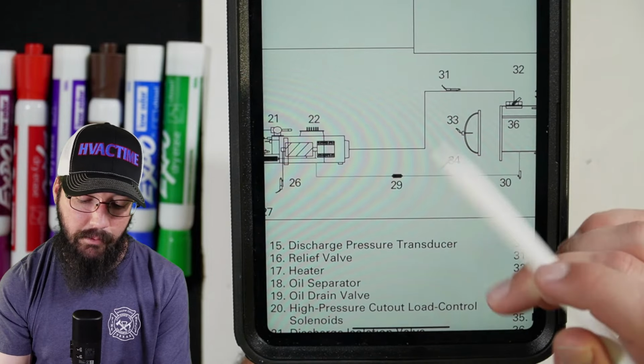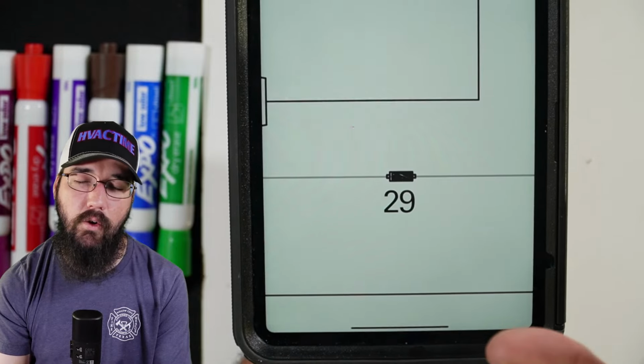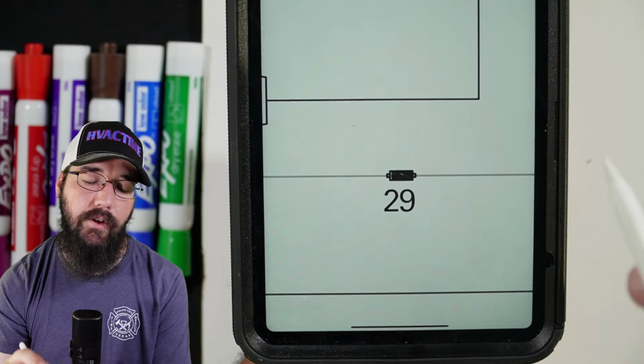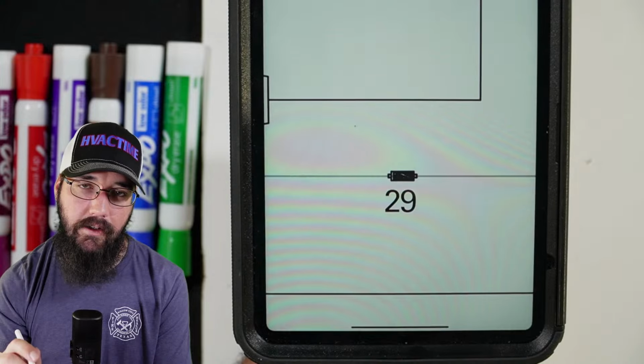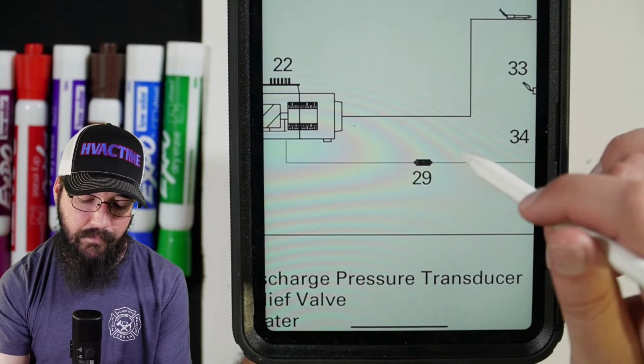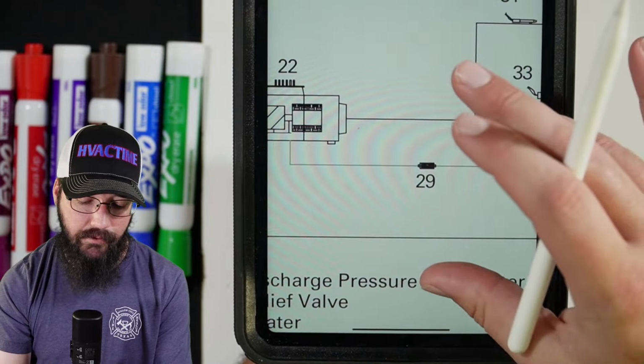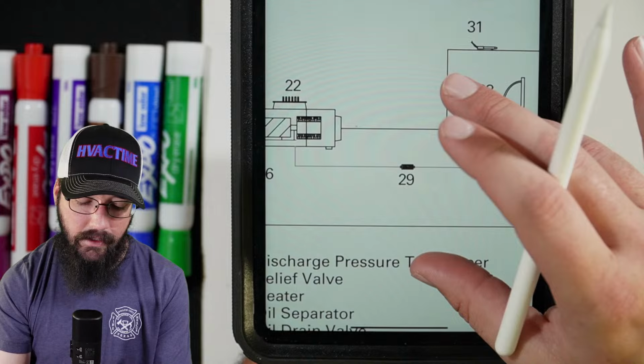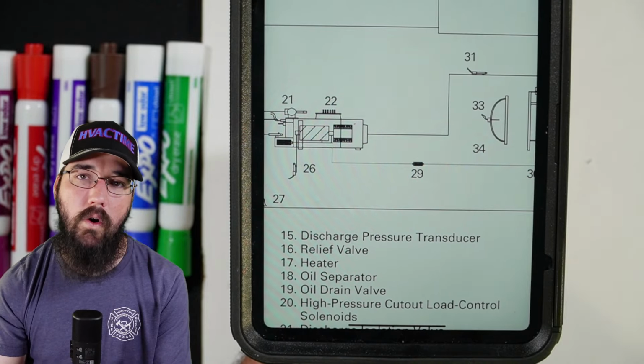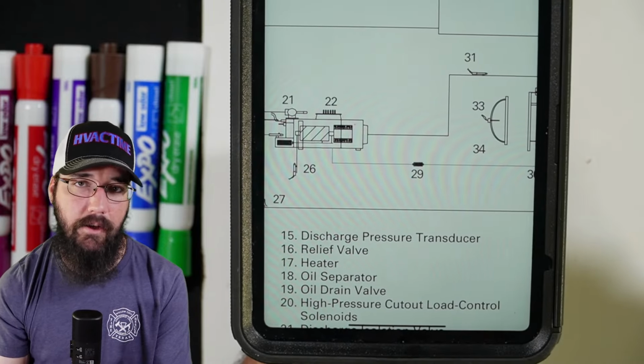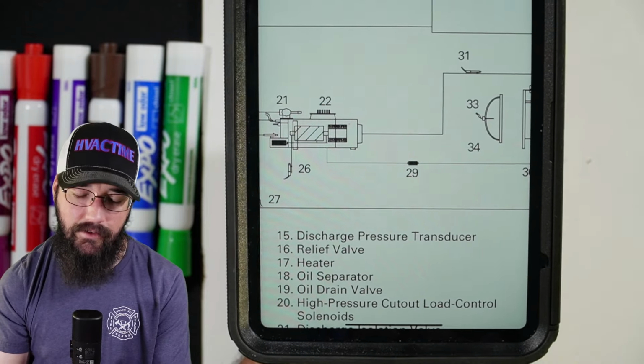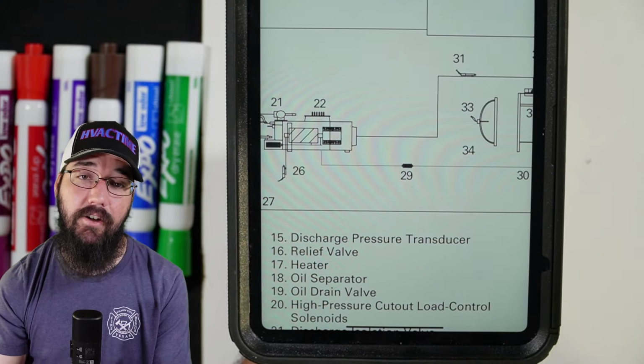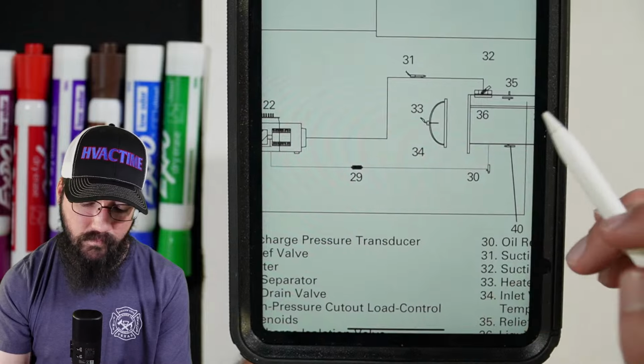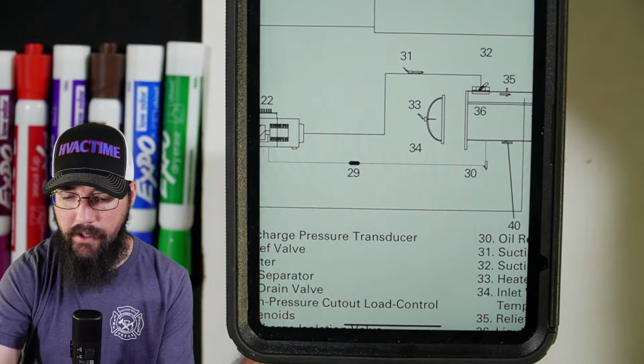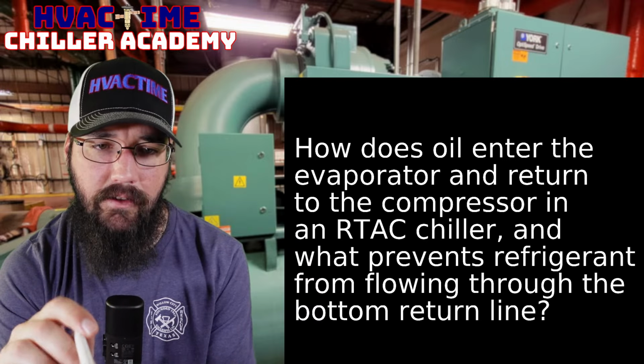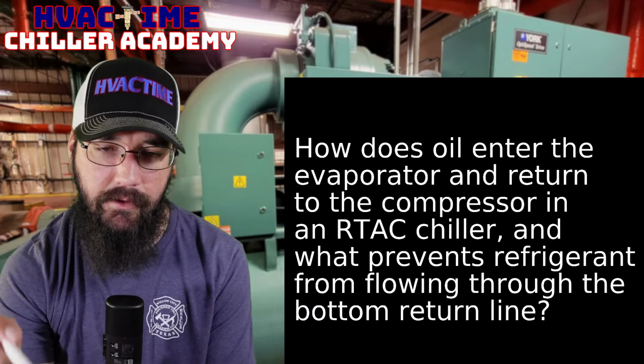And we process it through a filter. Okay, no, I'm sorry, I called it an oil filter. It is a dryer, just an oil line dryer, just a regular dryer you would have. There's nothing special about it. It's a filter dryer, and it's there to process water that might get introduced at any point, right? So if we have water, some minor acids, things of that nature, that's what that filter dryer is there to capture. That's its purpose. So the other part of your question was, how does it enter the evaporator and return to the compressor? Okay, we talked about that.